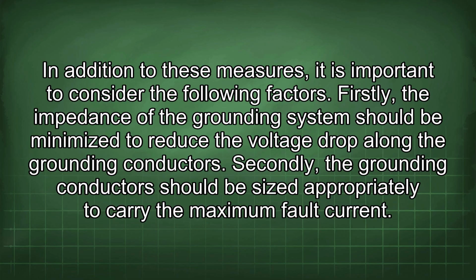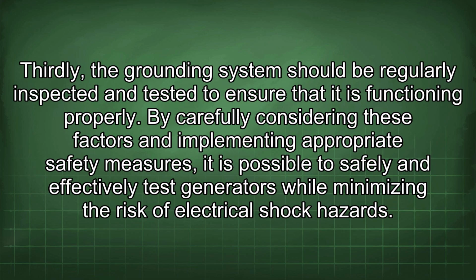Firstly, the impedance of the grounding system should be minimized to reduce the voltage drop along the grounding conductors. Secondly, the grounding conductor should be sized appropriately to carry the maximum fault current. Thirdly, the grounding system should be regularly inspected and tested to ensure that it is functioning properly. By carefully considering these factors and implementing appropriate safety measures, it is possible to safely and effectively test generators while minimizing the risk of electrical shock hazards.